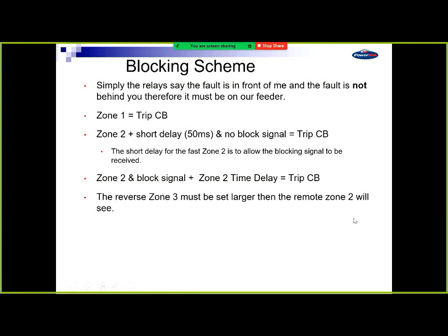So I've explained all of that there. The way we set our zone 3 is you use the remote zone 2, so you need to be able to see further back behind you than what I can see beyond you. That's the logic behind it. So my remote zone 2 setting, we multiply by 120% for a safety margin. We take off the feeder impedance because that's between us, and then we multiply the lot of that, so that multiplying me by 120% is the absolute furthest I'm going to see. You then go 20% over top of that, less the feeder impedance, that's your setting. So that's the basis of it. So you don't need to do reverse zone 3 studies, you just need to get the setting of your remote end feeder. So you have to set these both ends together when you're doing this.